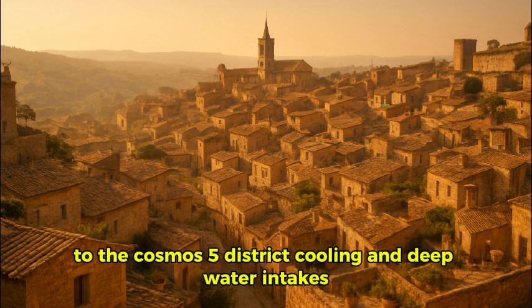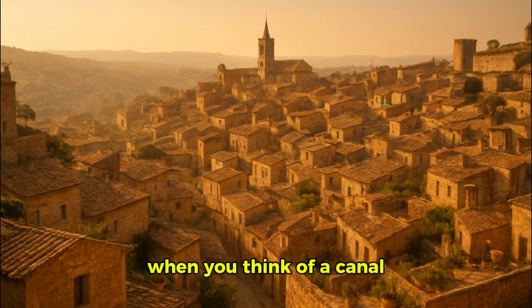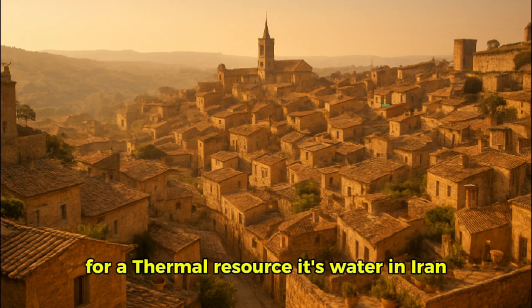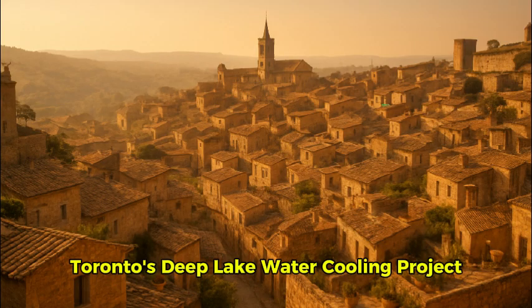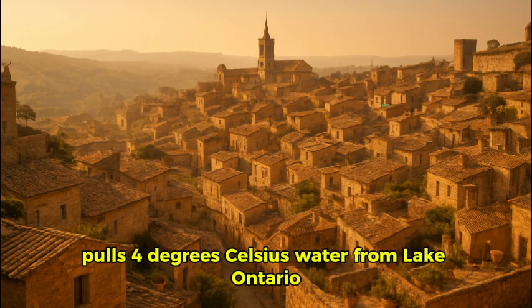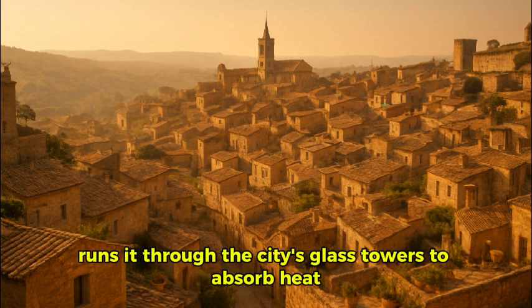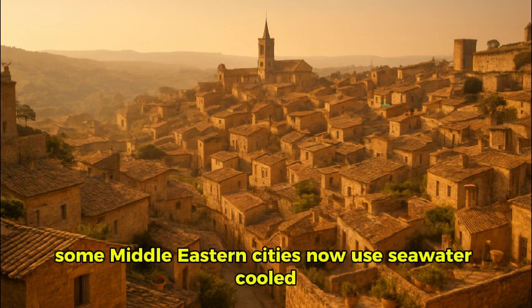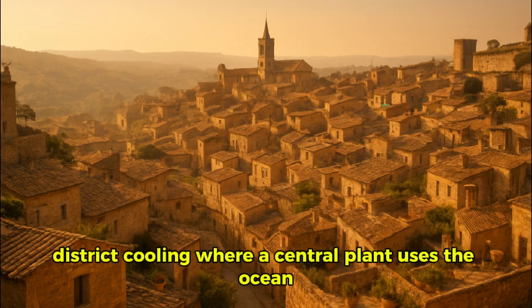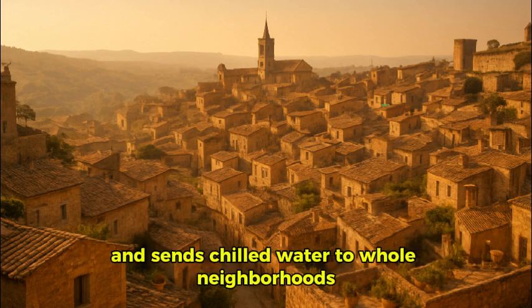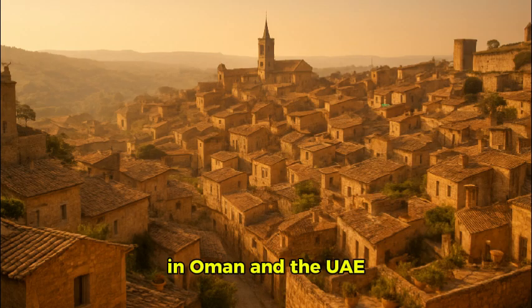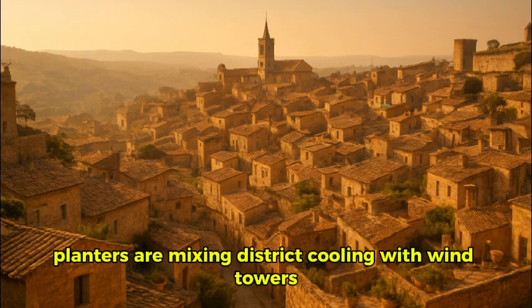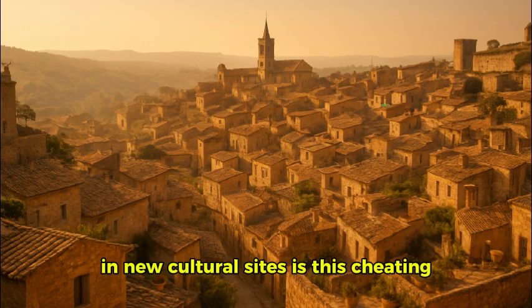5. District cooling and deep water intakes. When you think of a qanat, think of a passive distribution network for a thermal resource. It's water in Iran. In Toronto, it's cold. Toronto's Deep Lake Water Cooling Project pulls 4 degrees Celsius water from Lake Ontario, runs it through the city's glass towers to absorb heat, and then returns it. Some Middle Eastern cities now use seawater-cooled district cooling, where a central plant uses the ocean as an immense heat sink and sends chilled water to whole neighborhoods. In Oman and the UAE, planners are mixing district cooling with wind towers in new cultural sites.